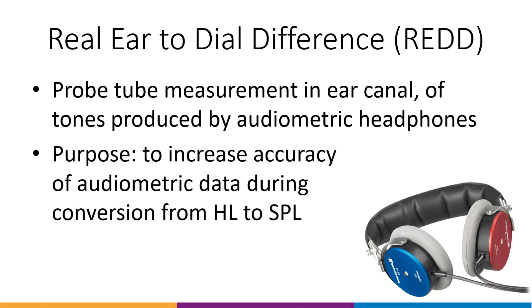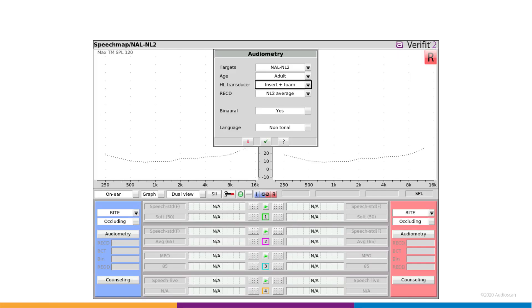The REDD can be used to predict the Ear Canal SPL for threshold and uncomfortable loudness level, UCL, when headphones have been used for audiometry, and can improve the accuracy of audiometric conversion from DBHL by individualizing the transform versus using average data.